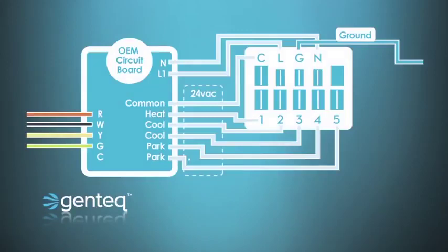In this example, we see that the manufacturer has wired all of the taps of the X13 motor back to the OEM circuit board. In this case, we would be able to make any of our speed changes right at the circuit board without having to go over to the motor. However, because all we have is a heat tap, a cool tap, and some places for the unused speeds to be parked, we don't know what the unused speeds do, and we would need to find the other chart in the manual that tells what all of the connections on the X13 do. So if the problem with the HVAC system is that the motor is not running, now we can focus on troubleshooting the motor itself, and that's what will be covered in the ECM service guide.